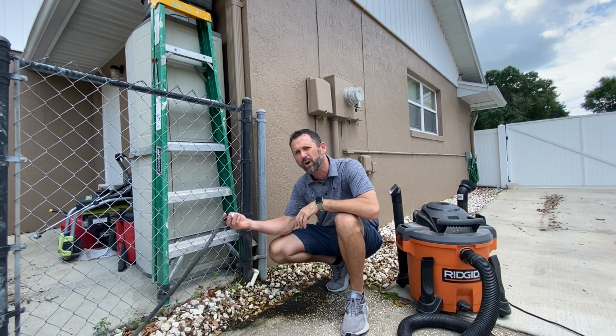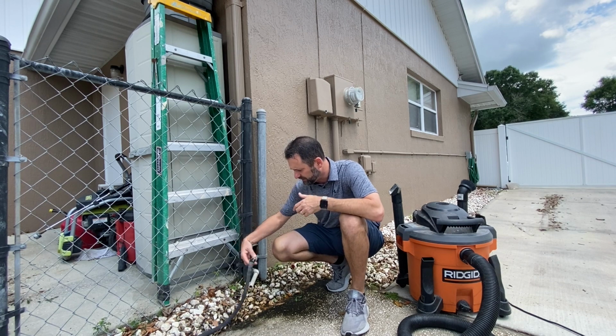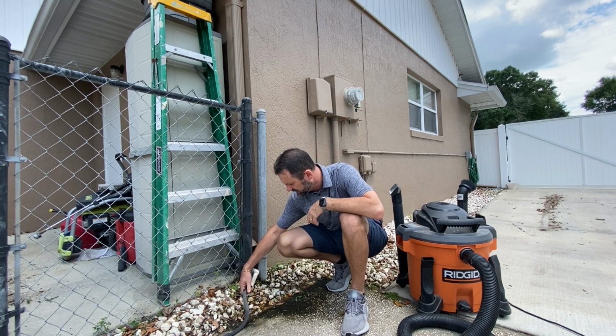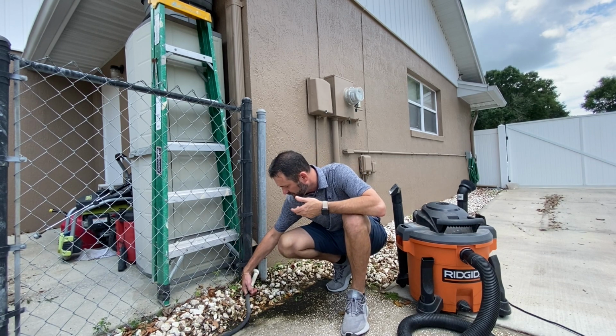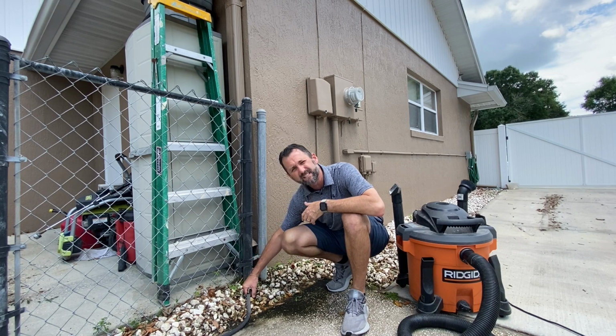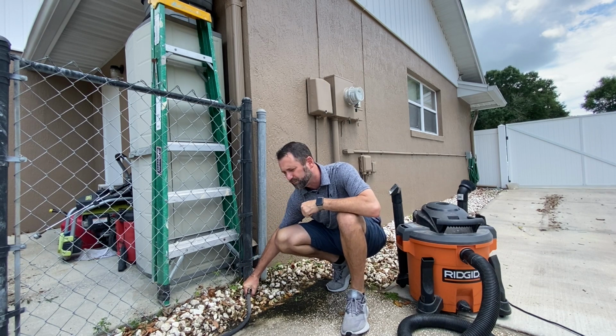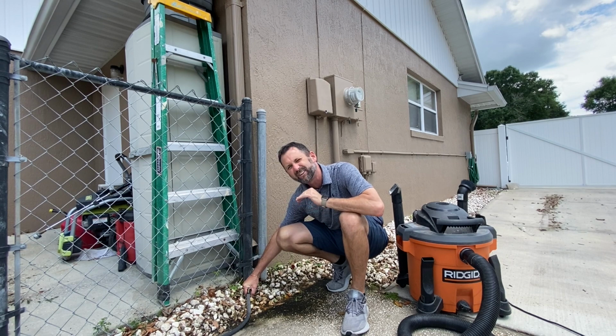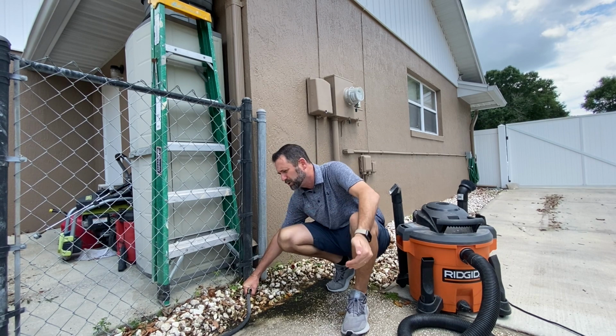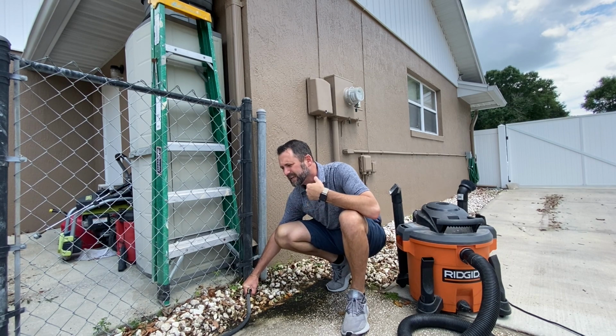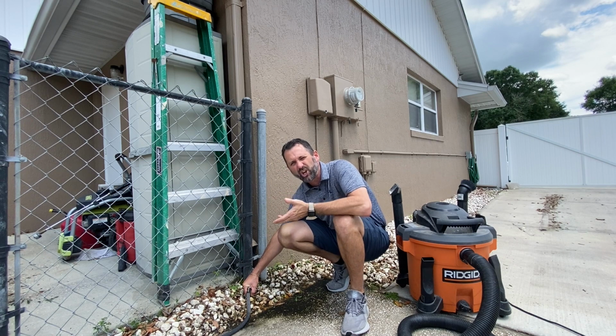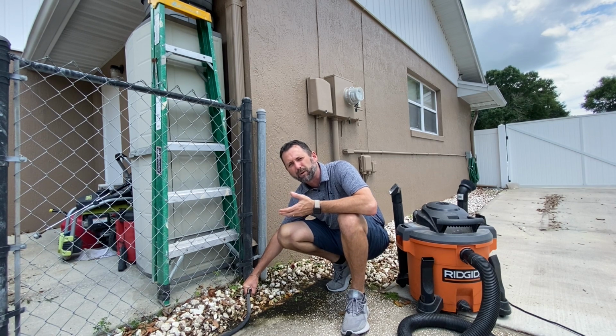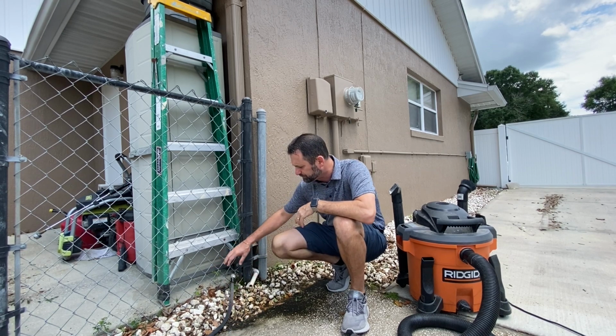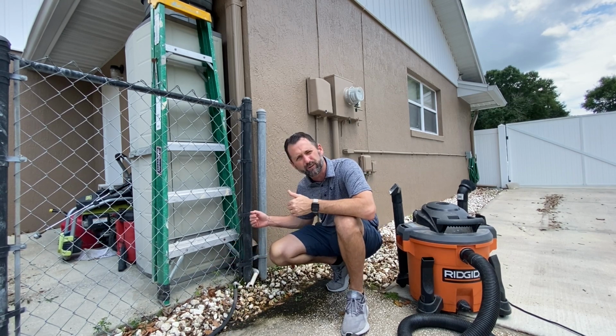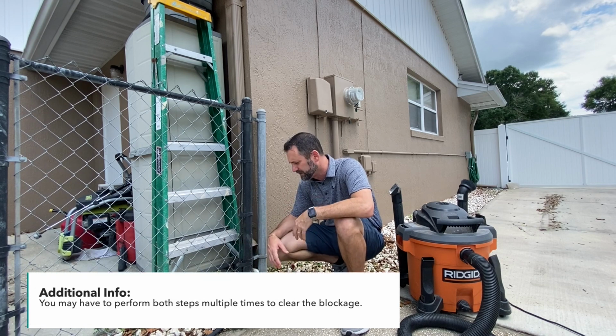You would take a water hose, your standard water hose. You would turn it on regular pressure or full pressure, what have you. You'd hold it to the end of the PVC pipe, cup your hands around there, turn it on full flow, put it on there for about 10 or 15 seconds at the max, because you're pushing water back up into the system, into a system that's already shut off because the drain line's not working properly. So we're just wanting to budge that blockage loose so that you're able to get the water flowing back again so that your system will turn on.